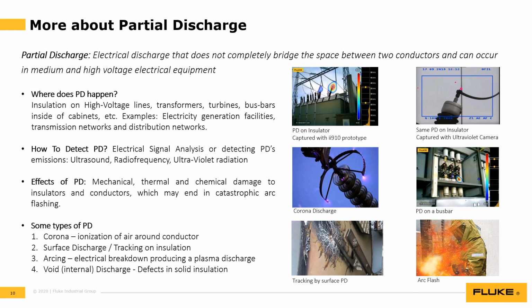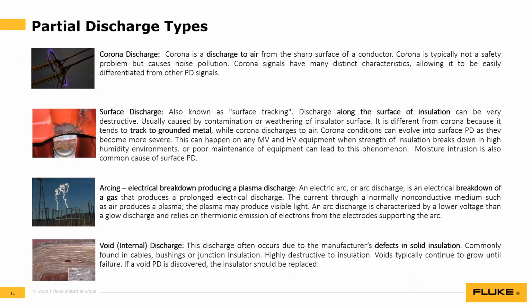And over time, the repeated energy that is produced there will degrade the equipment. It's actually the insulation that it's degrading in there. And through that degradation it has effects, mechanical, thermal or chemical breakdown, depending on the type of partial discharge and the equipment. We can talk about the different types of partial discharge. I've broken it down into these 4. Sometimes there are different words used, but it's really some of the same things.